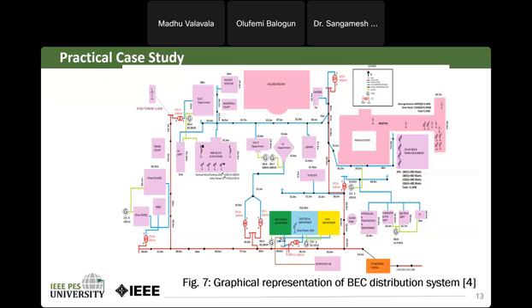These two radial feeders feed the separate engineering departments, starting from civil, electrical, and mechanical engineering, which have a distribution transformer center behind them, earlier rated 100 kVA, now upgraded to 400 kVA, with a voltage rating of 11 kV by 415 volt. The primary and secondary sides of this distribution transformer center can be seen.